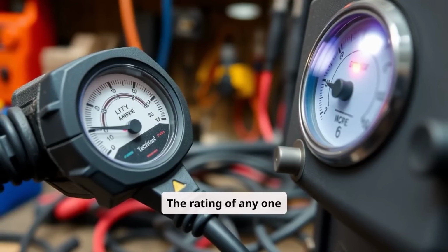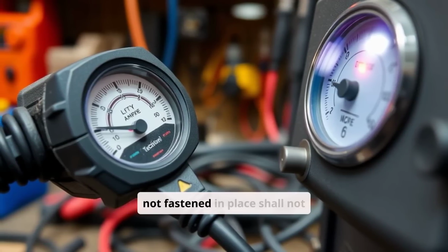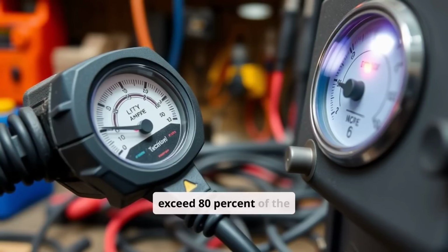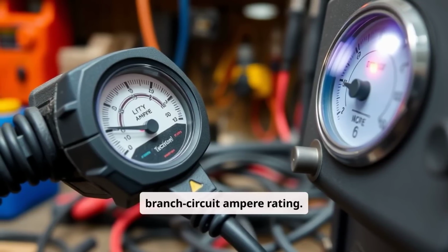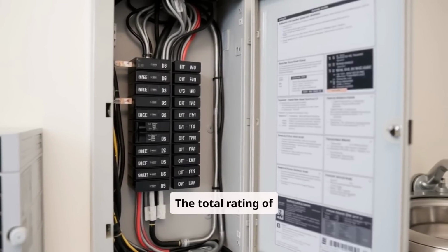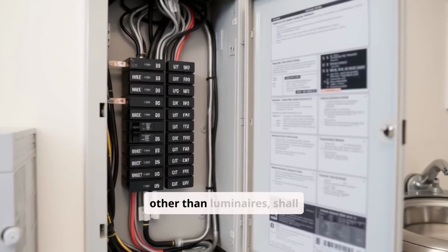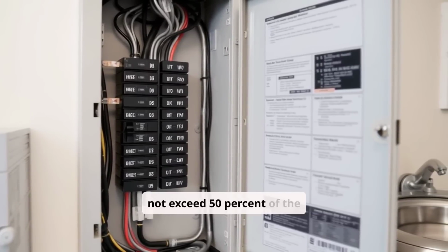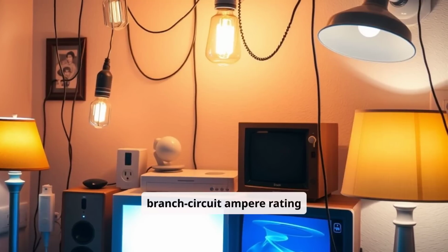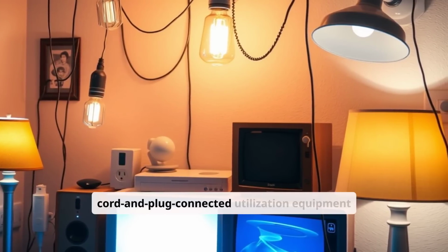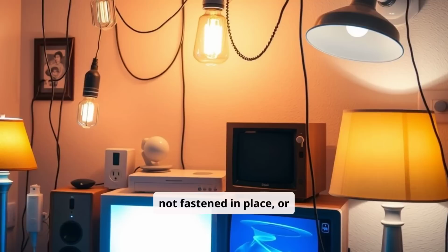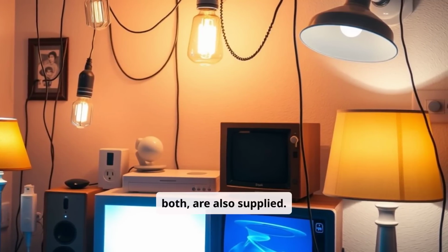The rating of any one cord and plug connected utilization equipment not fastened in place shall not exceed 80% of the branch circuit ampere rating. The total rating of utilization equipment fastened in place, other than luminaires, shall not exceed 50% of the branch circuit ampere rating, where lighting units, cord and plug connected utilization equipment not fastened in place, or both, are also supplied.